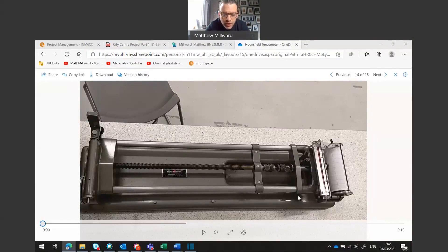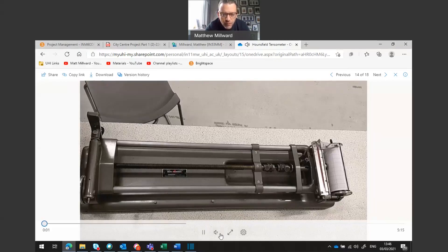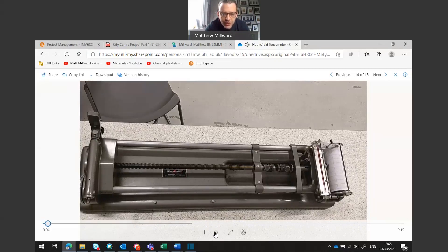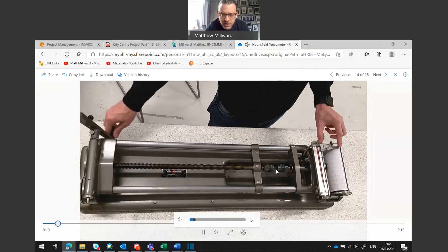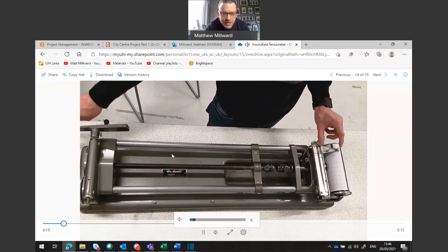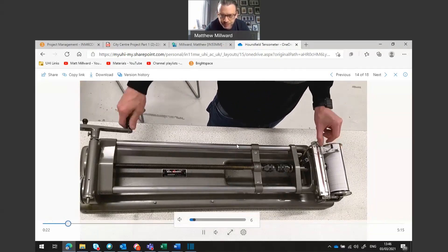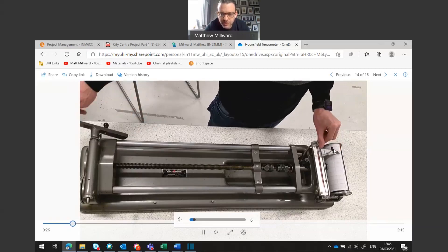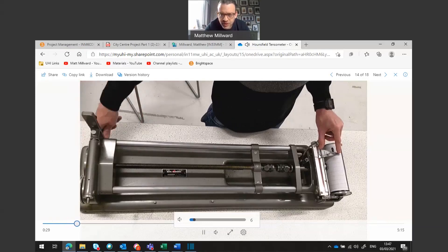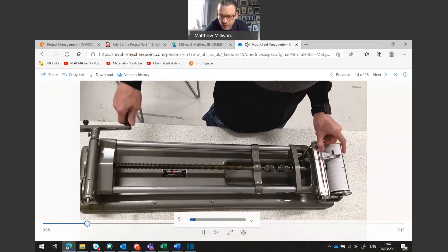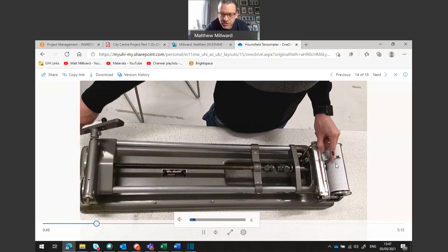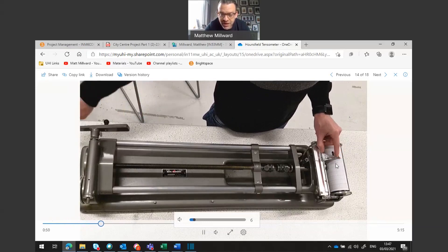We have a video here that was done previously by one of our technicians and I'll talk through what is happening. You can see the Hounsfield tensometer testing machine and there is a steel sample placed in between two clips. The technician is winding the handle and applying a tensile load. As the load is being applied, the strength is being monitored using this gauge here. We have a piece of graph paper on this drum and it is rotating. As the strength is increased the technician will place a dot on the graph to show the relationship between how much the piece of steel is being stretched and how much load is being applied.